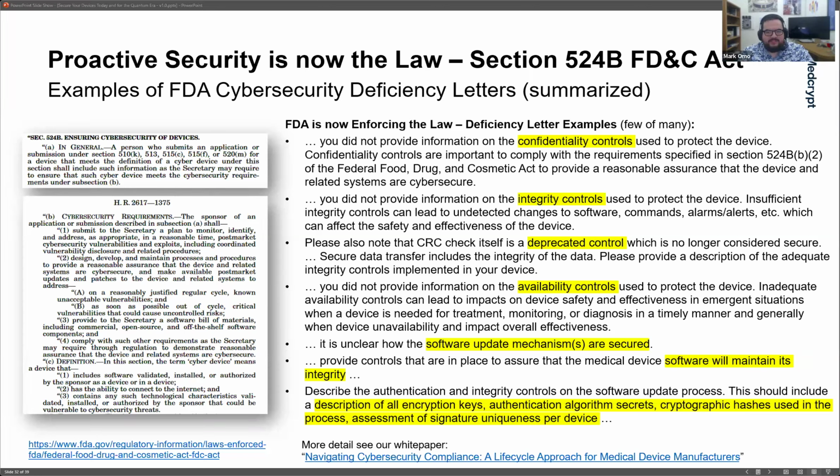I wanted to add on a little bit, which is, we get this question a lot: our FDA examiner allowed this cybersecurity last time, and you guys are telling us this isn't okay. They said it was okay. That's fine. Well, it turns out that even if the FDA says it's okay, the threat actors may be better than the FDA. And even if it's not the law, that doesn't mean that the hackers and the people who are trying to cause patient harm are taking their foot off the gas.